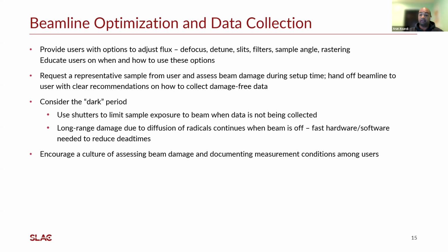And I do agree that it would be a good idea to include some details about the sequence of the measurements, especially if there's some possibility that each measurement was done on the same spot and potentially damaged the sample to some extent. But of course, these measurements should be done starting with low flux, using mitigation measures like attenuating filters to start with conditions that are least likely to cause this beam damage, so that all successive measurements are good quality.